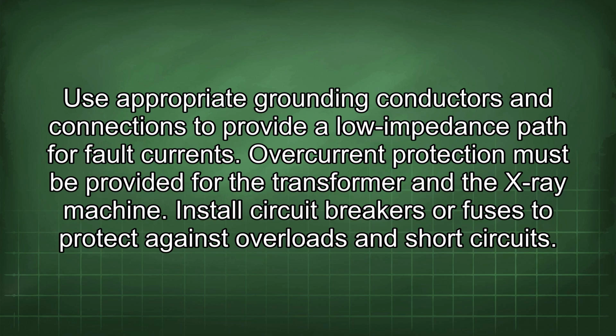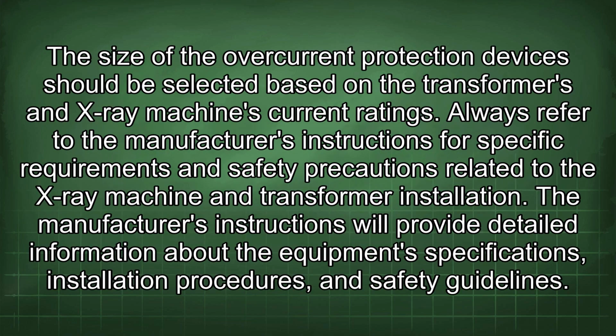Overcurrent protection must be provided for the transformer and the X-ray machine. Install circuit breakers or fuses to protect against overloads and short circuits. The size of the overcurrent protection devices should be selected based on the transformer's and X-ray machine's current ratings.